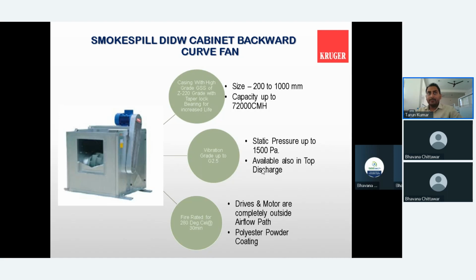At the same time, when the area is very compact and there is no space to install the fan at the terrace, or there is no location, like you have a very compact location and you want a low dB fan, we should always prefer the cabinet fan. A cabinet is nothing but an enclosure which gives some sound reduction. So in that case, there is a fan available with DIDW also, and the motor will be outside the airflow path. In that case, you can see the arrangement in the slides. Here we have kept the motor outside the airflow path, and it will be very compact in design, since it is a DIDW fan with suction on both sides. For that reason, the fan size will come down compared to the SISW fan.